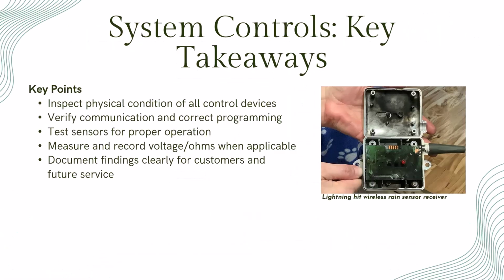Before we leave a site, the goal is to make sure every control component is physically sound, communicating properly, and programmed to run efficiently and legally. That means inspecting the hardware, verifying the settings, and testing devices like rain sensors so we know they're actually working. When required, we also benchmark voltage and resistance readings so future problems are easier to diagnose.